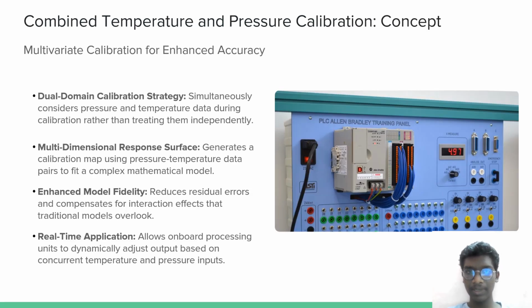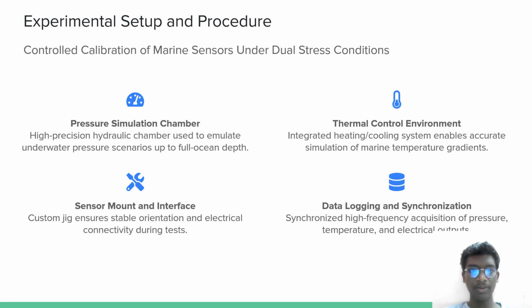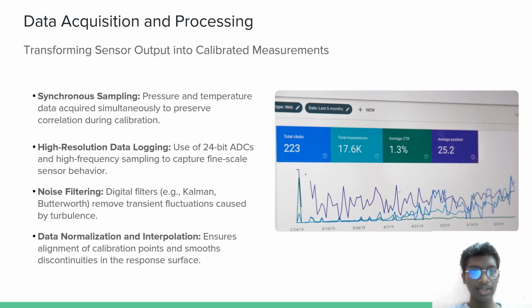Combined temperature and pressure calibration concept. Dual domain calibration strategy: multi-dimensional response surface, enhanced model fidelity, real-time applications. These are the benefits of combined temperature and pressure calibration. Experimental setup and procedure: pressure simulation chamber, thermal control environment, data logging and synchronization, sensor mount and interfaces. Data acquisition and processing: transforming sensor output into calibrated measurements, synchronizing sampling, high resolution data logging, noise filtering, data normalization, and interpolation.